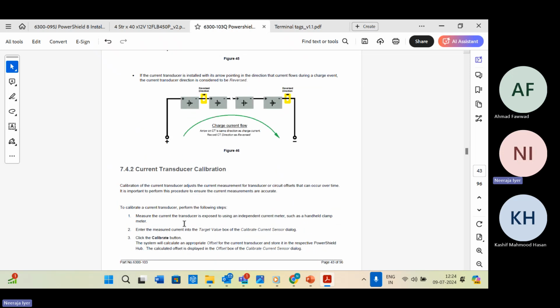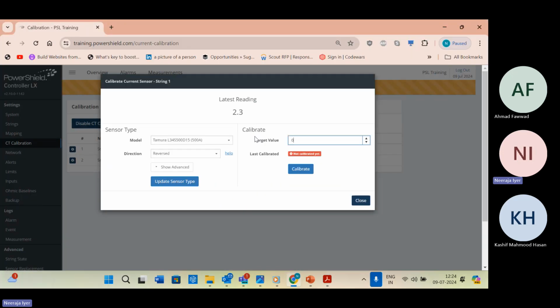So for calibration of the CT, the right way is to put an independent, recently calibrated handheld clamp meter on the string, measure the live current value, and enter that here in this box, target value. Usually it will be 0.2, sometimes 0.8, whatever the value is using a live calibration meter, you enter it and click calibrate. Is that clear? We should measure the value by an independent clamp meter, the live string current value.